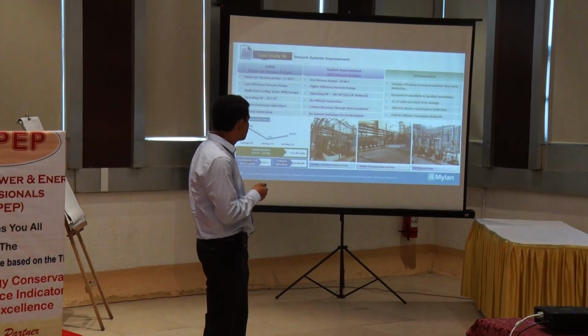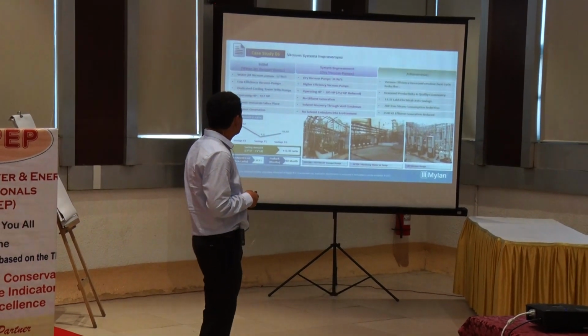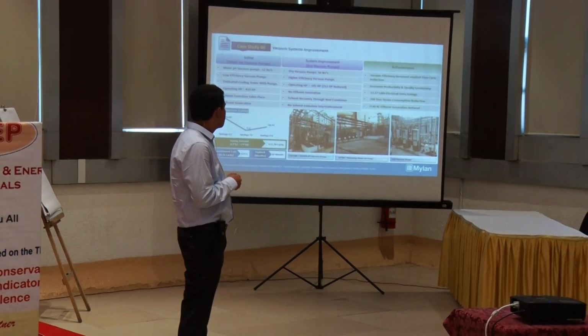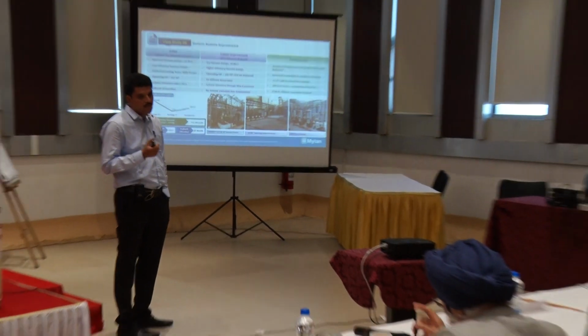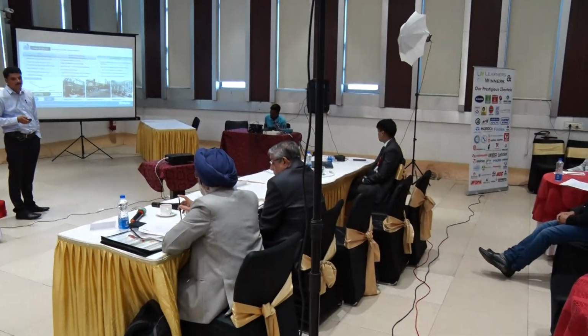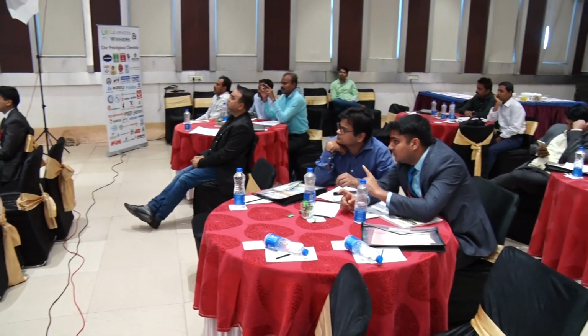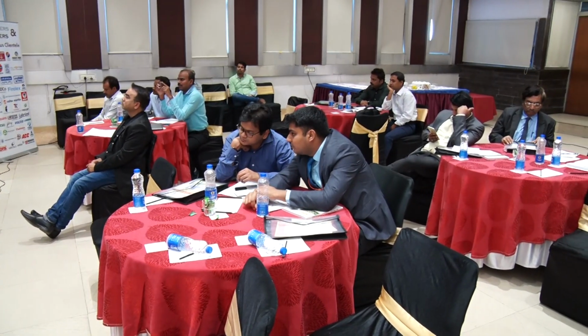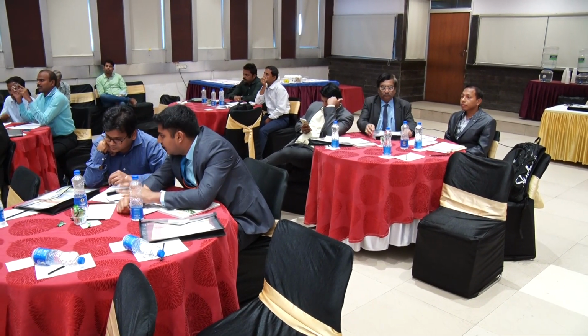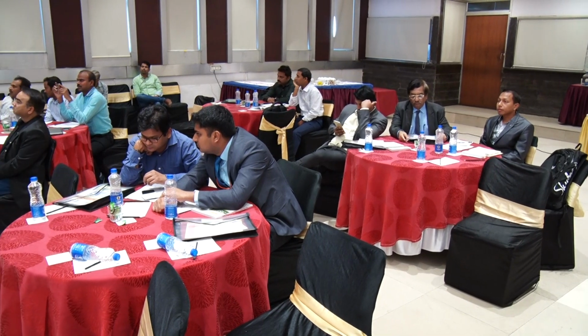So vacuum efficiency has increased, and productivity and quality consistency have increased. 13.37 lakh electrical unit savings, 288 tons. Earlier we used to have water ring vacuum pumps along with steam jets, wherever high vacuum is required. We have replaced all water ring and steam jets, and we are using 100% dry vacuum systems in the entire plant. The payback is 10 months. So these are the results we got.